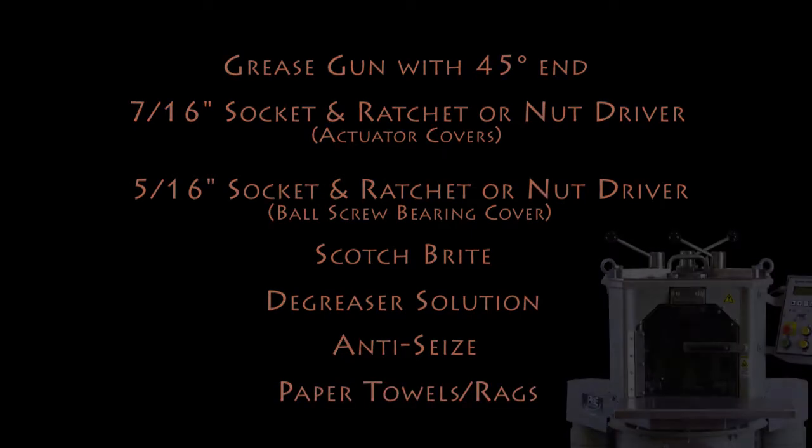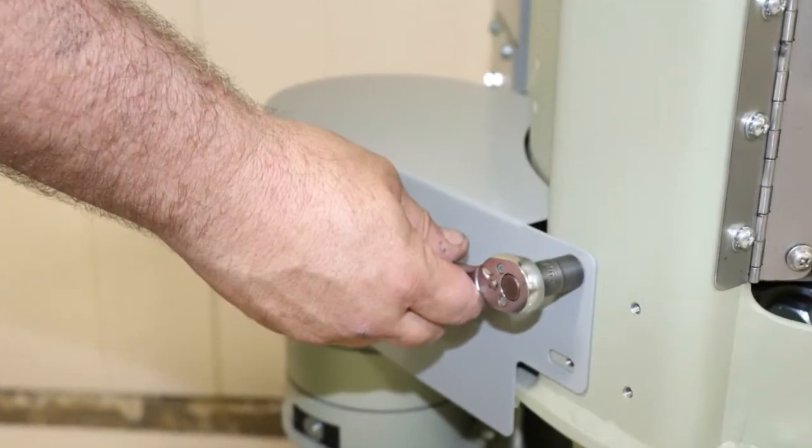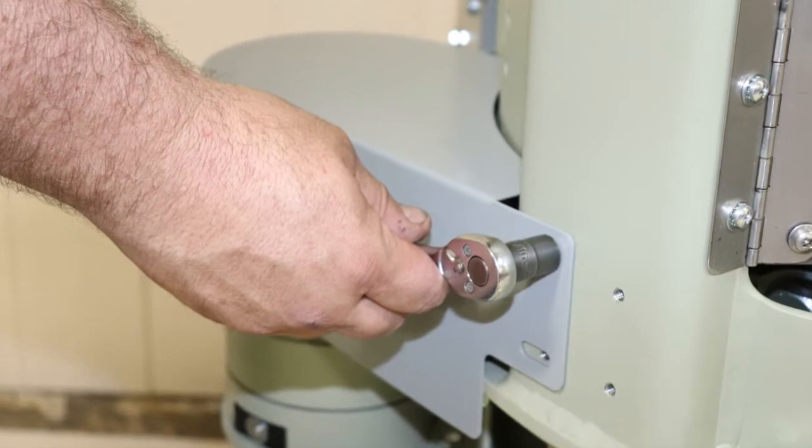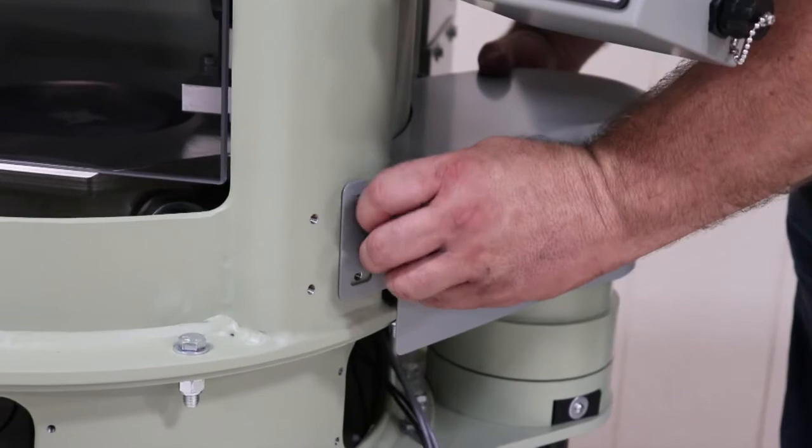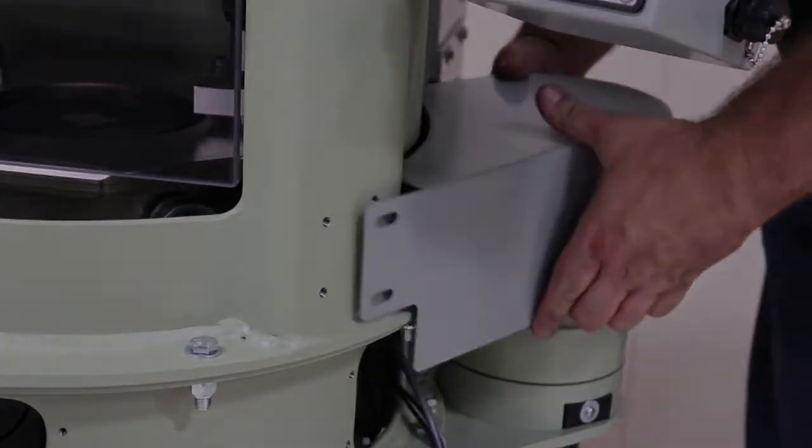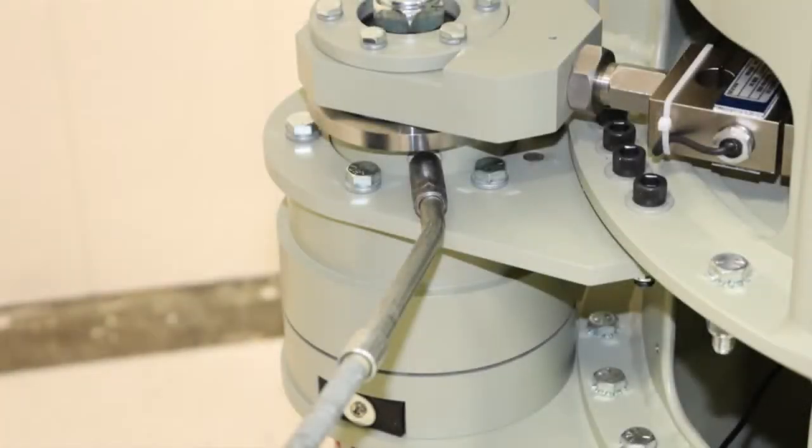Begin by using the ratchet and 7/16 inch socket or 7/16 inch nut driver to remove the left and right side actuator covers. Using the grease gun, grease the two grease fittings on each actuator.